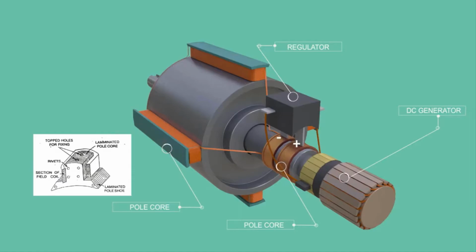With variation of load on the generator, the terminal output voltage will vary. It is desired to keep the terminal voltage within a specified limit. An automatic voltage regulator helps in achieving this. Voltage regulation can be easily achieved by controlling the field current. If the terminal voltage is below the desired limit, the regulator increases the field current. This will result in an increase in terminal voltage. If the terminal voltage is above the specified limit, the reverse is done.